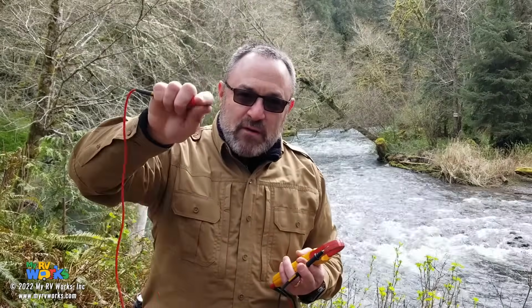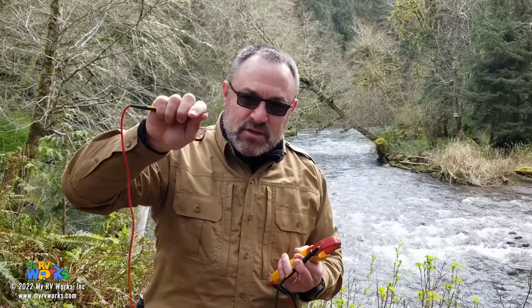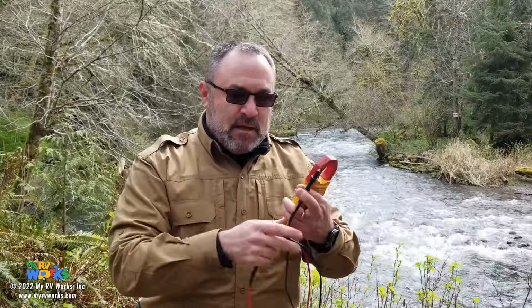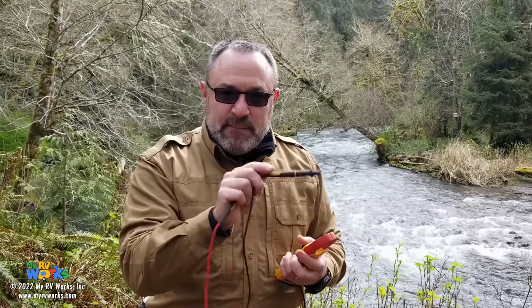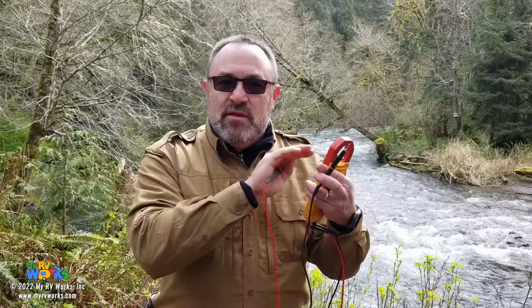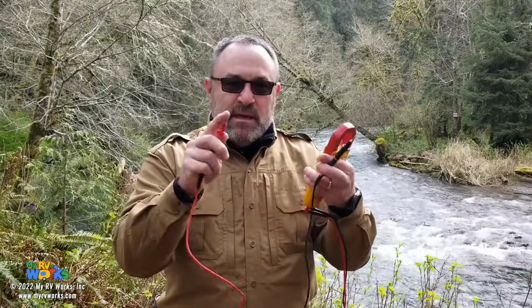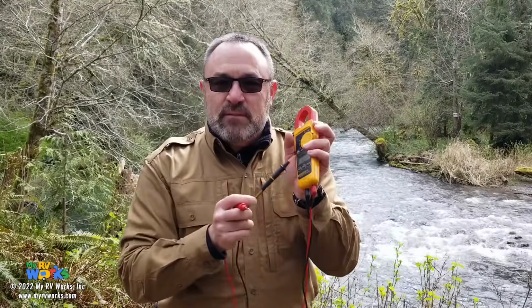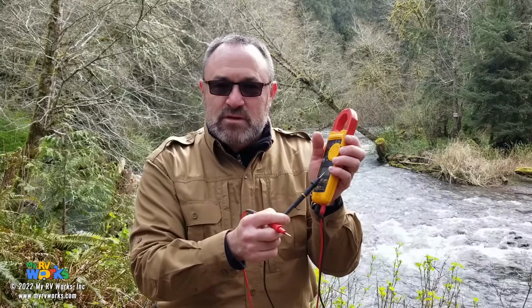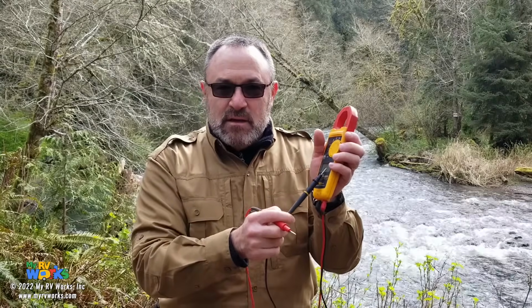When you take the red wire and hold it onto that black wire that you just took out of your breaker, take the black lead and touch it to the neutral bus bar, where all the white neutral wires are screwed in. See if there's any continuity on your meter—it's going to show 0 ohms, or there's going to be a value there.